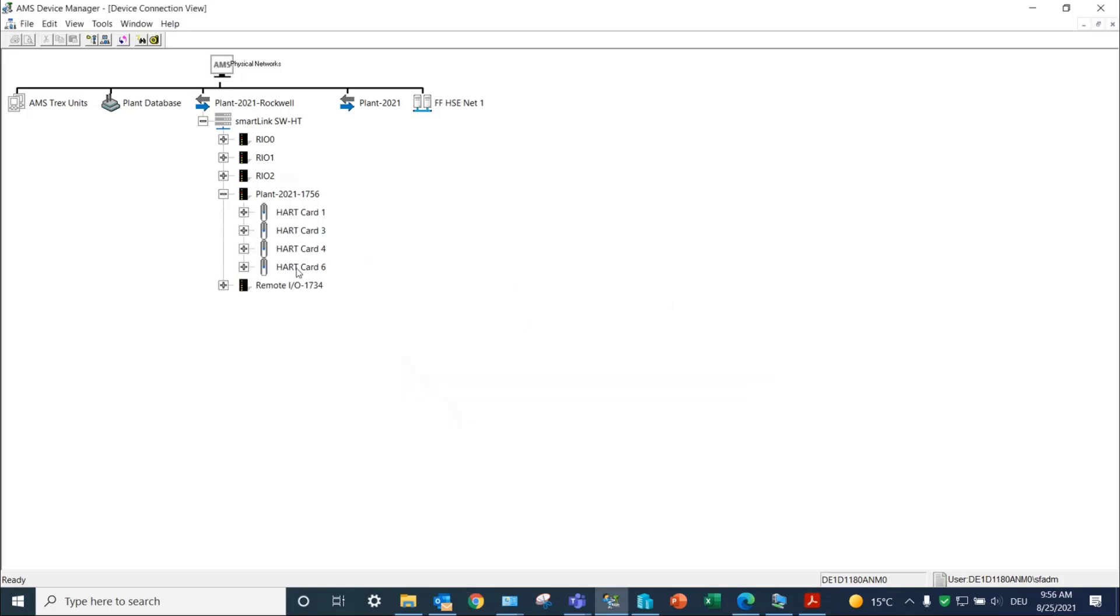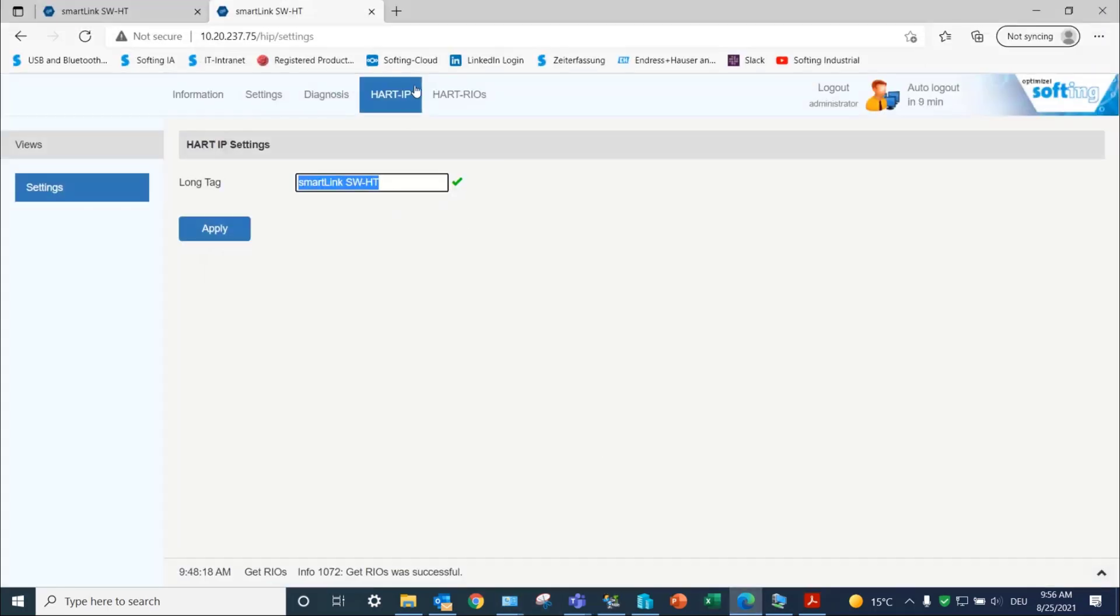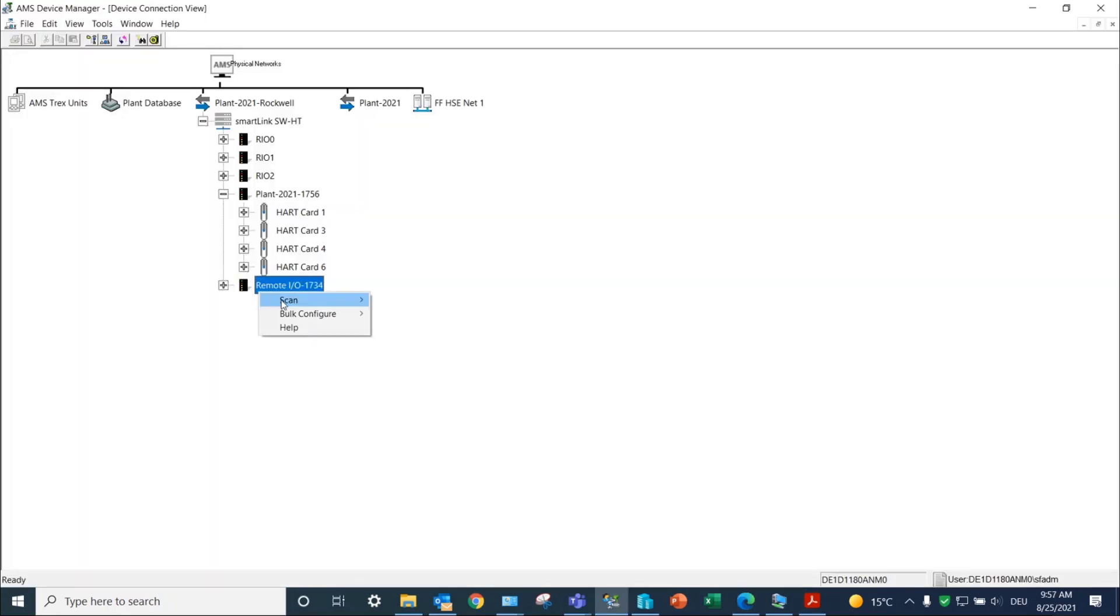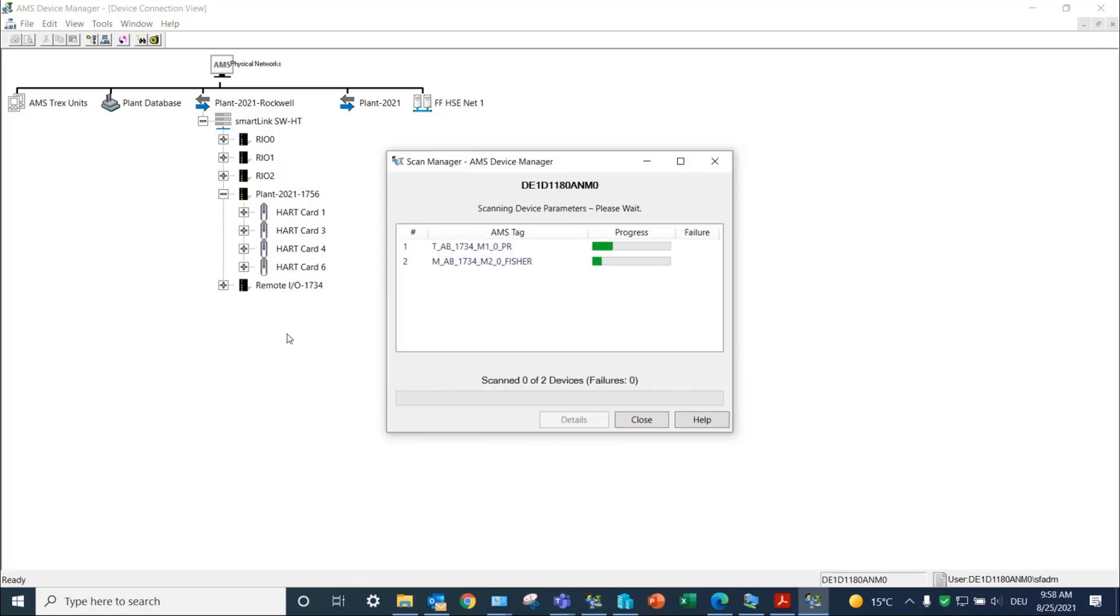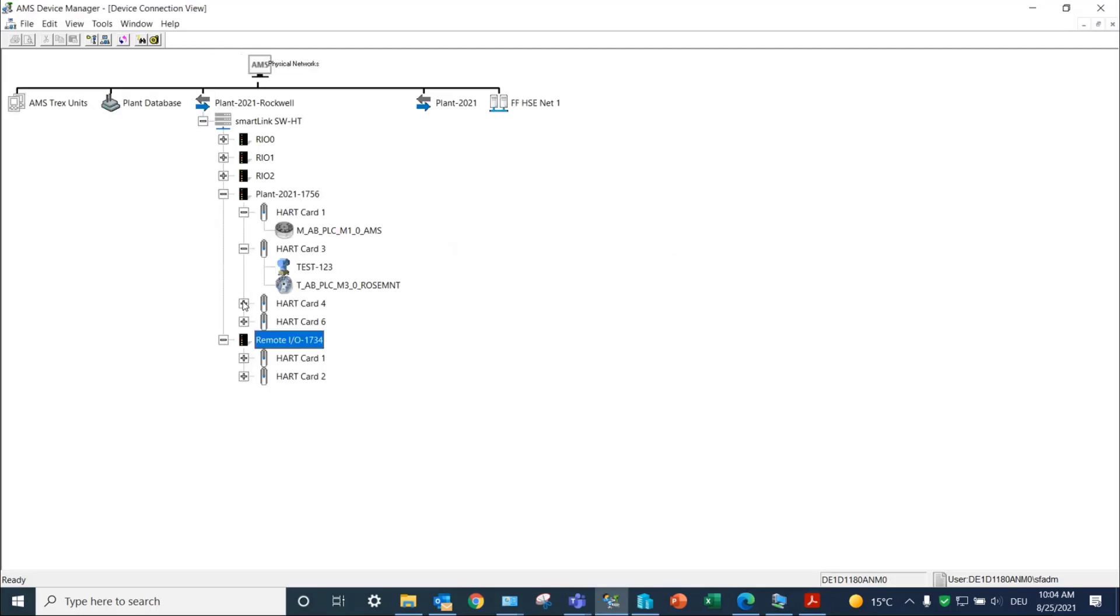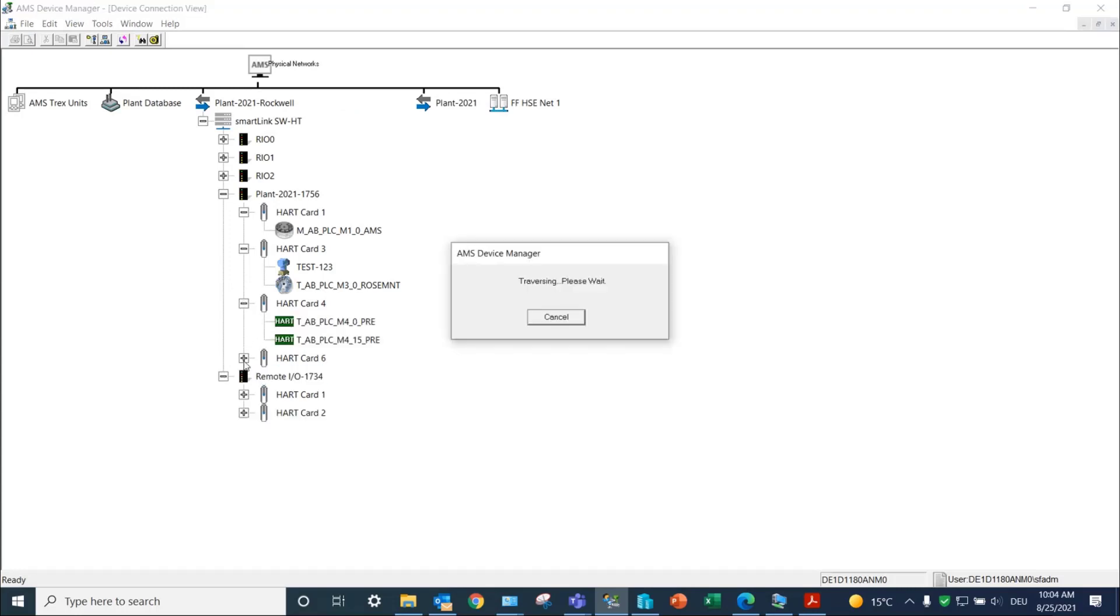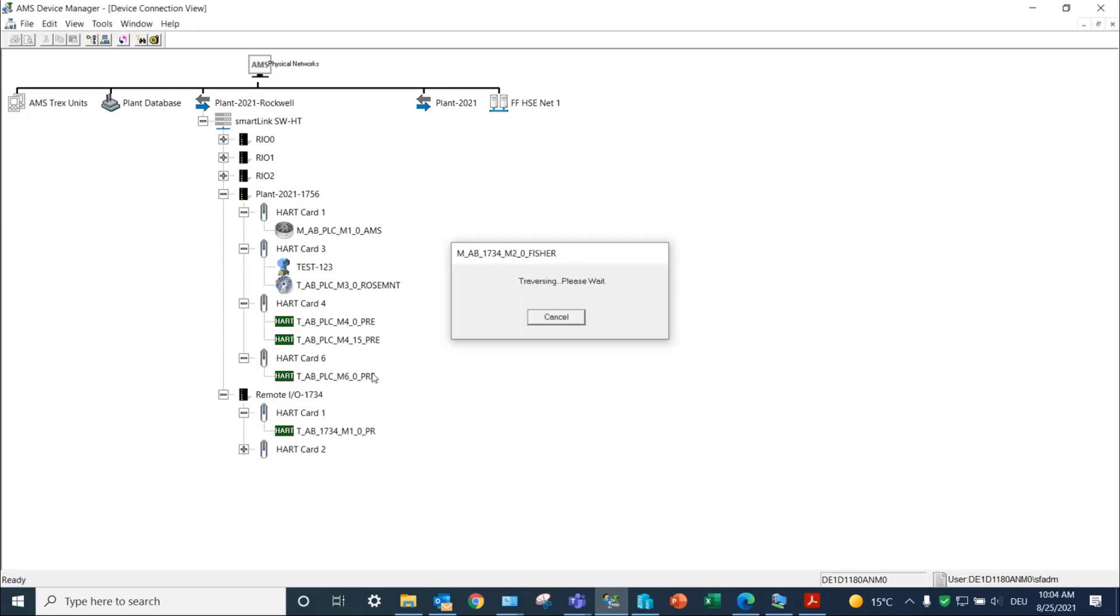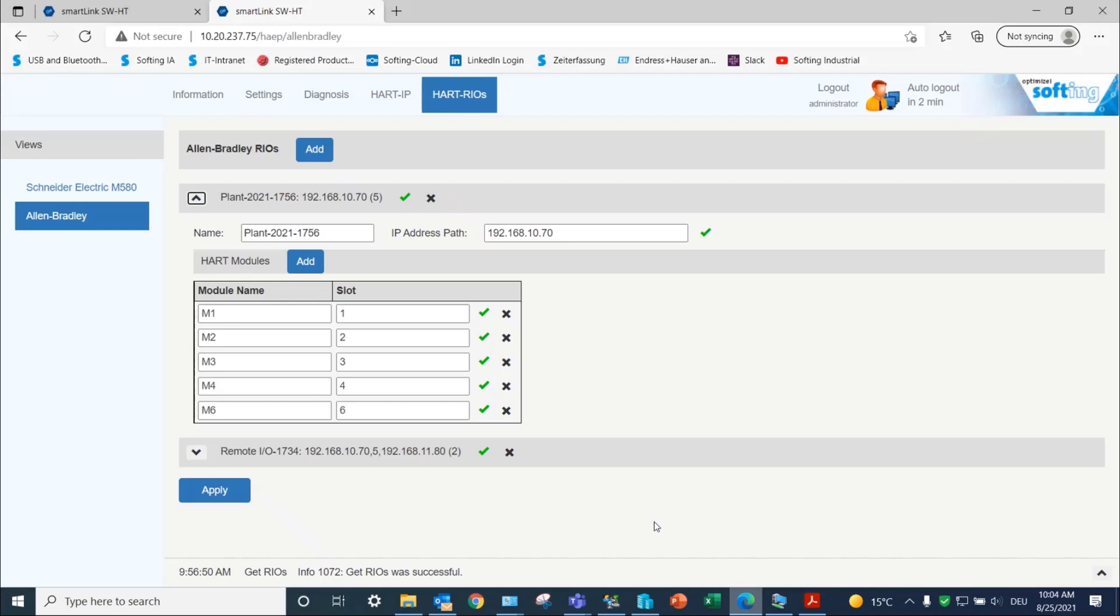HART card numbers represent the HART module slot numbers. Repeat the operation with the remote I/O 1734. After the scan, you can now click on the plus icon of each HART module to display the connected field devices. In our test, eight devices are discovered and correspond to devices present in the live list of the SmartLink web viewer.